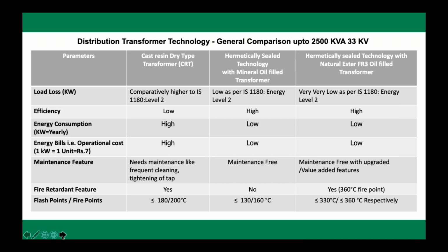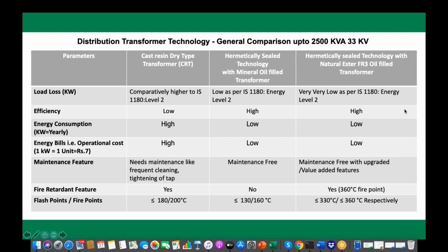Today, you get a product which is a 99.8% efficient transformer as against 90%. And why I'm putting a little doubt here is that if you look at the average loading of a transformer, be it a distribution network or, for the time being, some industrial application, the average annual loading of a transformer is typically 50% in any network. At that loading, liquid filled transformers, both mineral oil as well as ester filled, are far more efficient than a dry type transformer. At 50%, you really screw up the efficiencies in the dry type transformer.